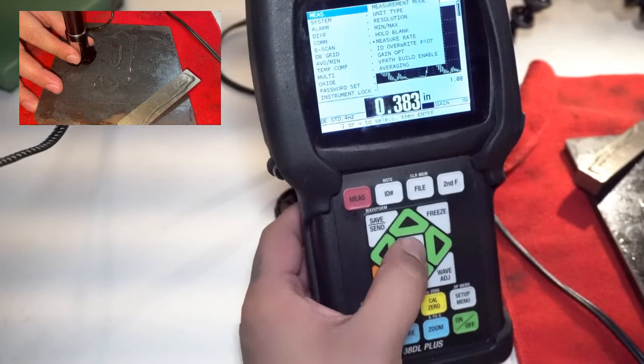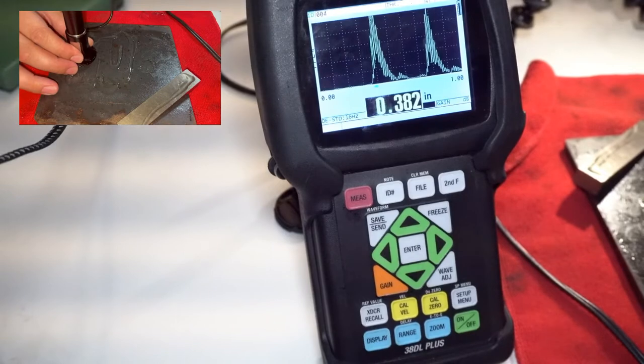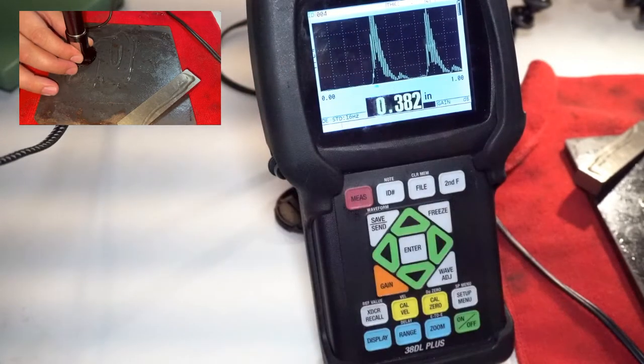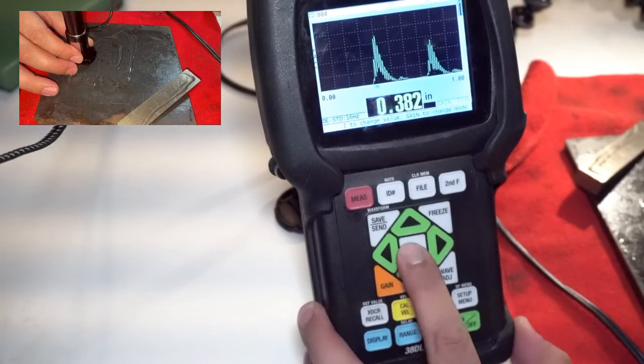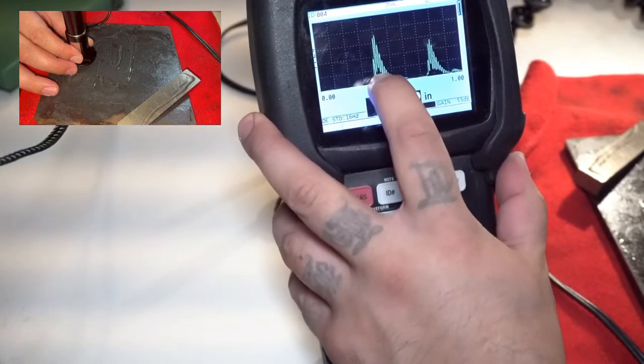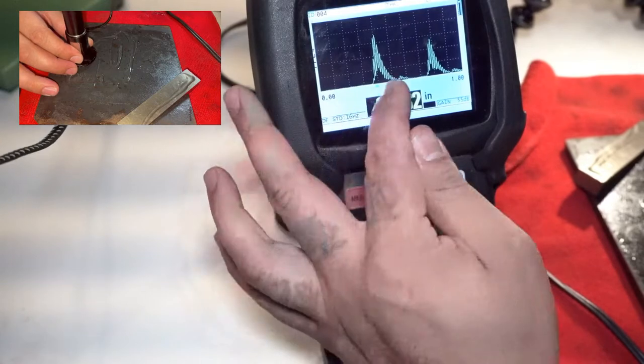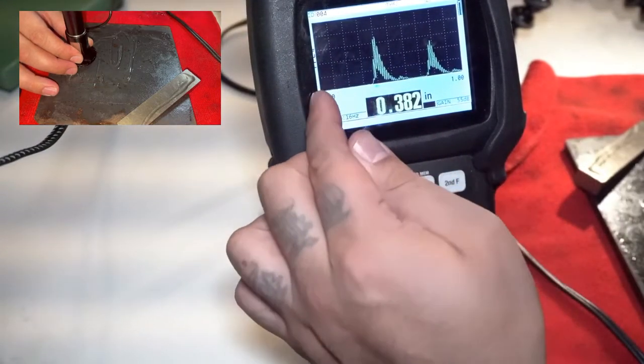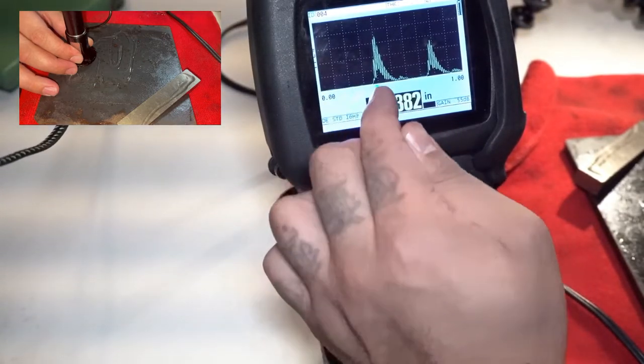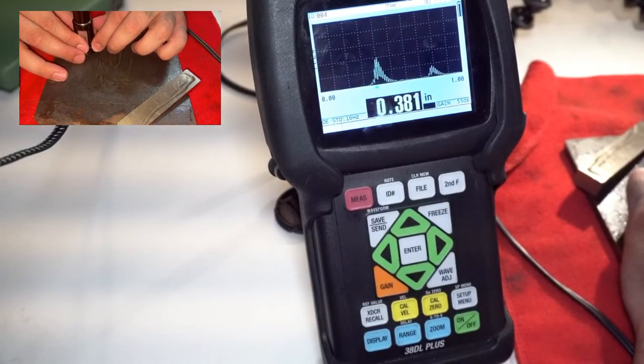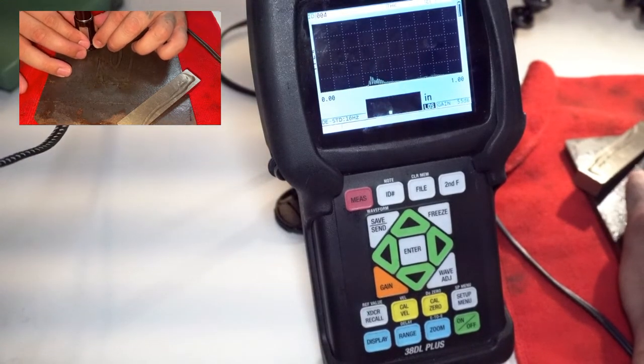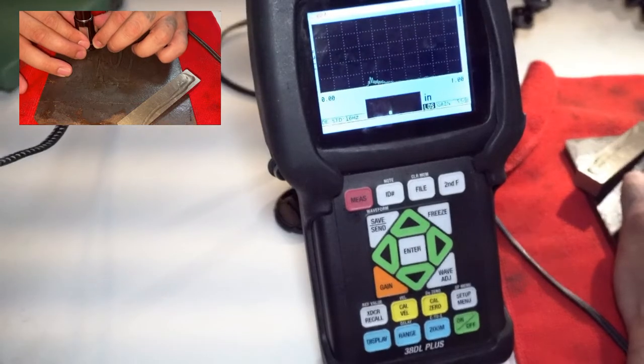So I'm going to change this to about 16 because this is what I'm comfortable with. And we're going to be watching our inspection area window, as I like to refer to it. And what we're looking for is a decrease in our back wall signal, and corrosion will tend to move to the left of the baseline because obviously from our entry surface to our back wall, we're going to see a lower numerical value here. So I'm going to go ahead and start scanning. And immediately as we scan, we see a decrease and we start to see a roll. See that? Now you notice that my numerical value has completely gone off the screen. There's blank.